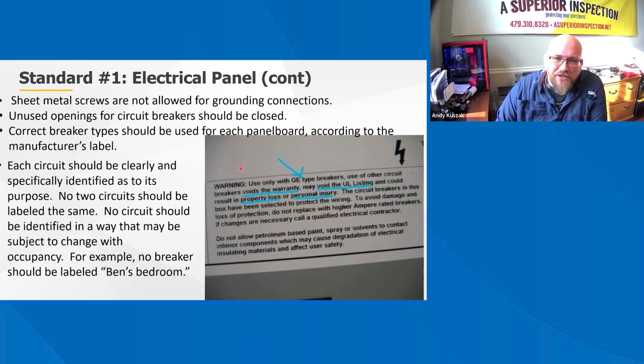And then we have this awesome little picture over here. So you should be able to find this or something like this on a lot of panels where it says, warning, use only with GE type breakers. Use of other circuit breakers voids the warranty, may void the UL listing, and could result in property loss or personal injury. The circuit breakers in this box have been selected to protect the wiring. To avoid damage and loss of protection, do not replace with higher amperage rated breakers.